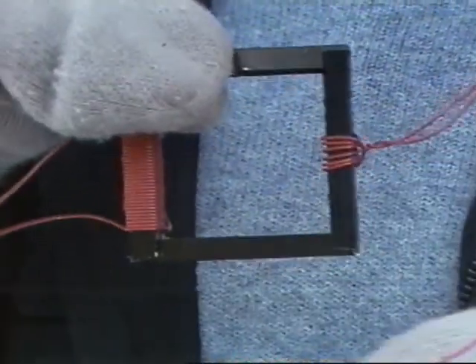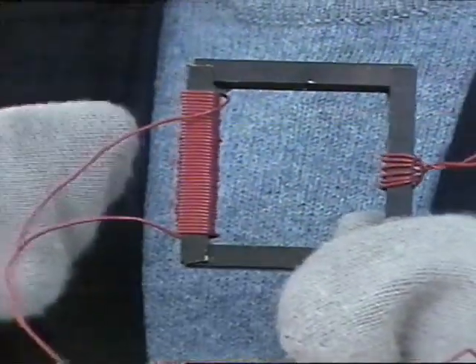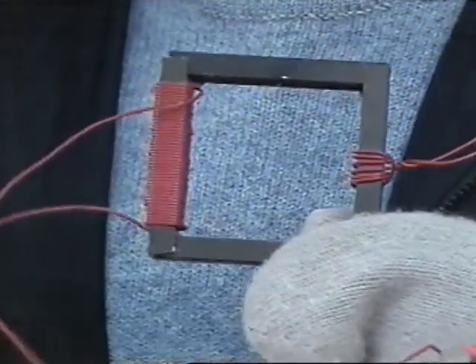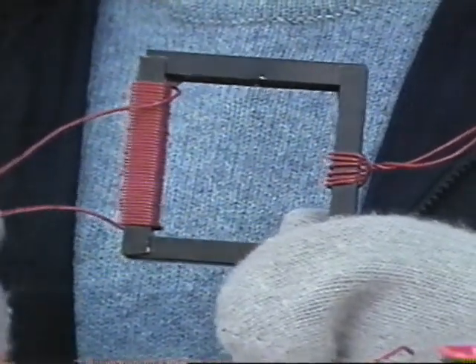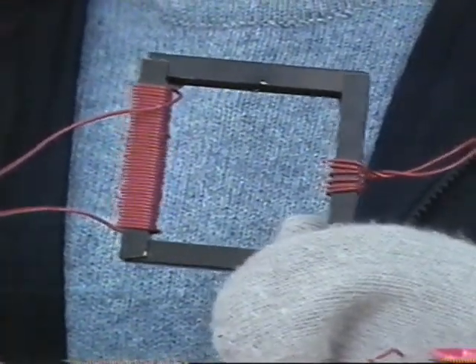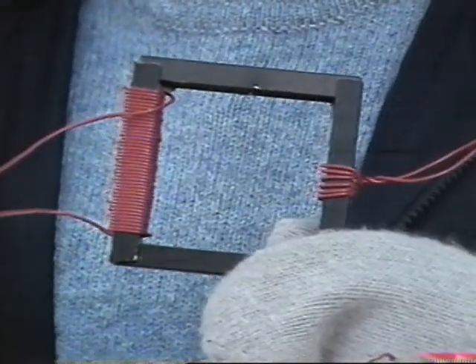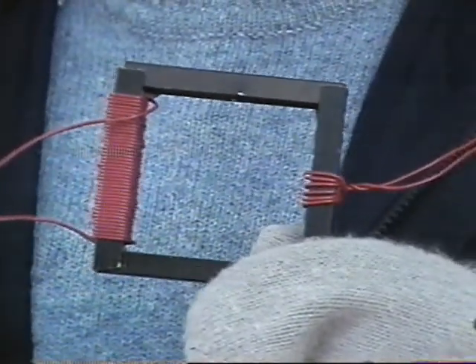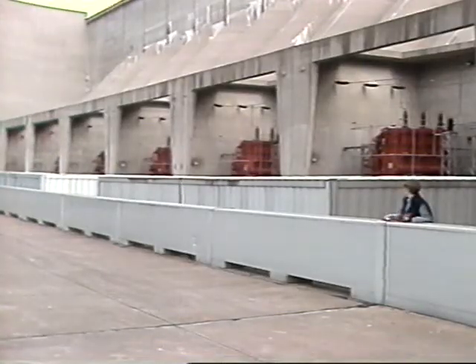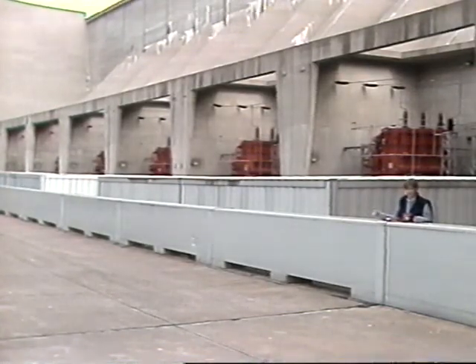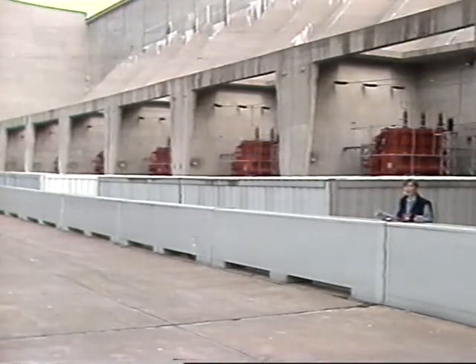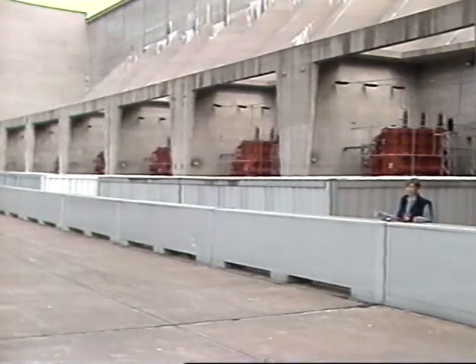This ring has 5 turns on this side and 50 turns on this side. When the current emerges from this side, the voltage has been increased by a factor of 10, but the amperage has been decreased by a factor of 10. These transformers change the 23,000 volts at 15,000 amps from the generators inside to 230,000 volts at 1,500 amps for transmission.